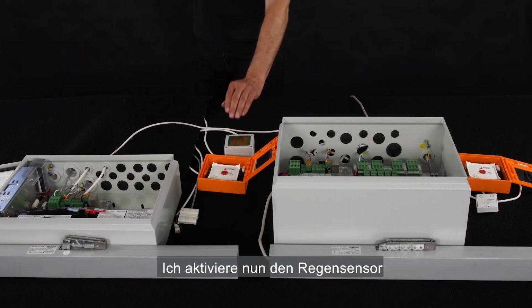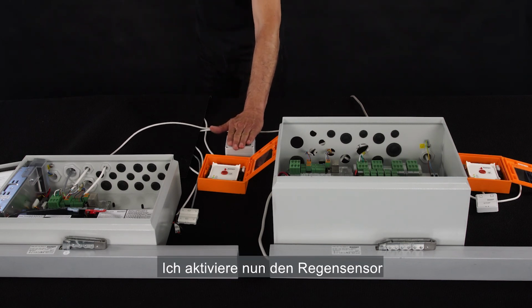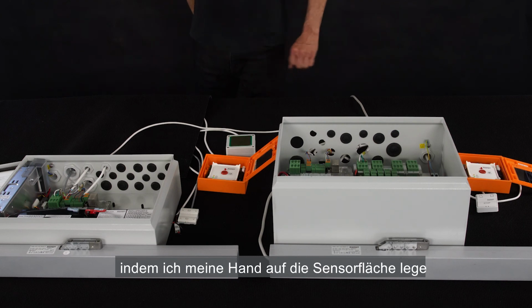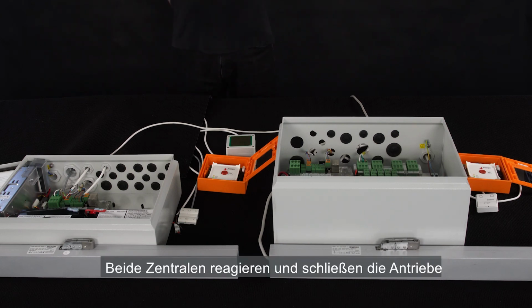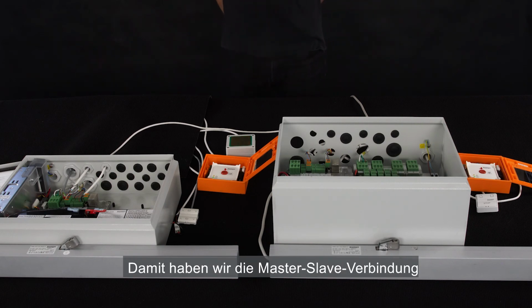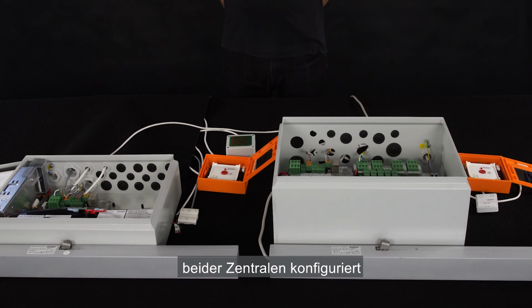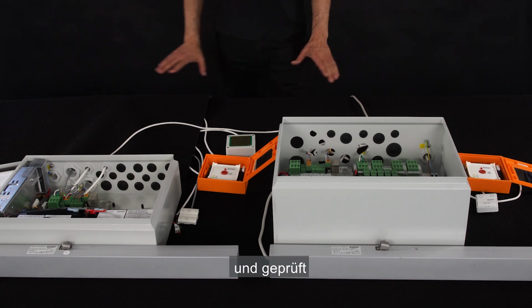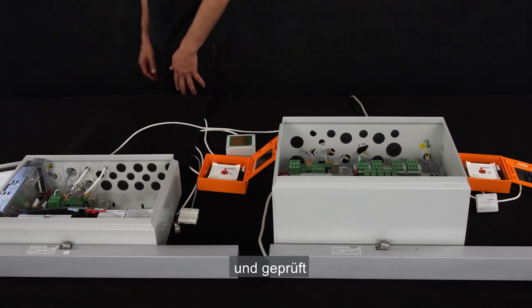When I activate the rain sensor by holding my hand over to create humidity, both panels react and close the actuators. We have now successfully configured and tested the master-slave connection of the two panels. They work now as one large smoke area.